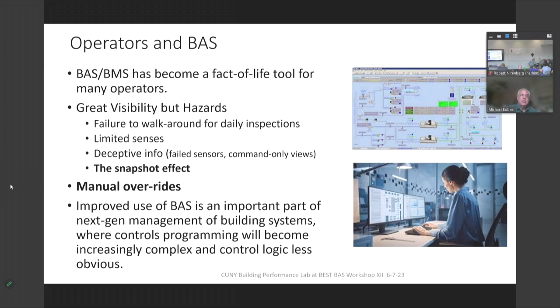The BAS also can provide certain kinds of deceptive information. We can have sensors that have failed in whole or in part, or lose calibration, so we get faulty information. And we're so tempted to believe it's correct that it takes us a while sometimes to see those failures.